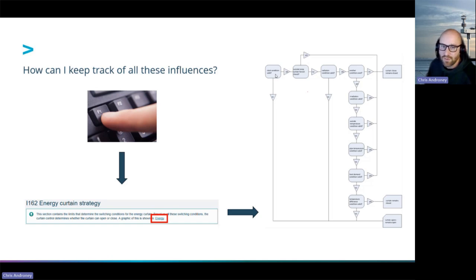It's a nice flow chart that says, okay, clock condition valid, yes. Is the outside temperature curtain force closed? Is that activated? Are we using any other influences? So you can go through this table in case you have a situation where the curtain should be closed right now, but it's not. Why is that? You can troubleshoot through here and say, okay, am I using this condition? Am I using this condition? It helps you troubleshoot that way.